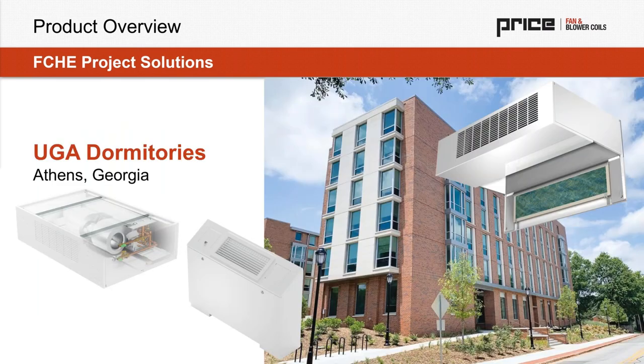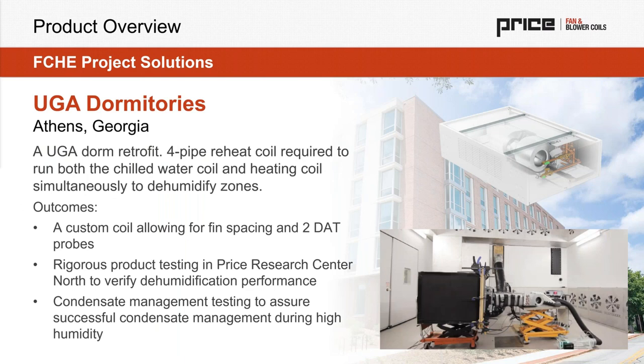Another good example, and one that's more representative of the commodity type product, would be the University of Georgia dormitories, which is actually very close to where I'm located here in Atlanta. In this project, they had some interesting constraints where these were retrofit projects. There was a lot of air infiltration through the envelope. They were wanting to retrofit and manage costs on the project. And so what they actually ended up requesting from us was a custom coil that could integrate two discharge air temperature probes, one sandwiched between a cooling and a heating coil, and the other downstream for the total unit supply air temperature. And this allowed them to run a dehumidification sequence of operation in particular.